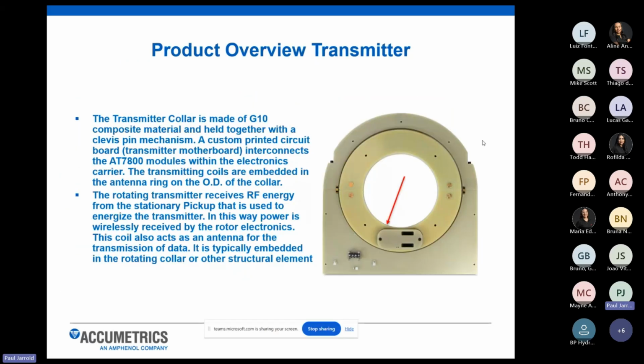So first, we're going to talk about the transmitter. Again, very similar to the EFRA midshaft system. It's a split collar design. This is manufactured out of a G10 composite material, which is a fiberglass embedded epoxy that's obviously non-magnetic, non-conductive. We have a trace of wire that's routed on the outside of this rotating transmitter collar, and then there's a stationary pickup antenna, which again has that turn of wire routed in that. Underneath this cover plate is the motherboard for the electronic modules for the 8 channels of RTDs. We provided this cover plate to give more protection of the electronic circuitry underneath.